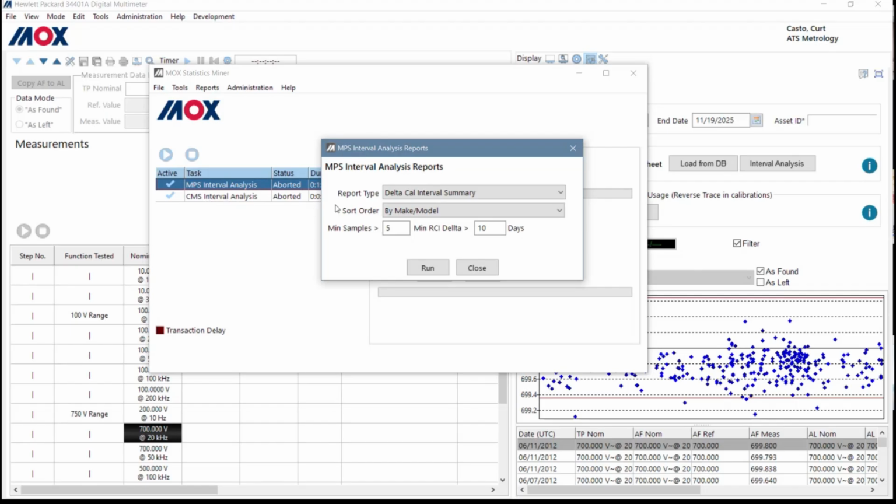And then of course, everyone talks about MPS and CMS. The CMS is your LIMS and the MPS is the part that processes the calibrations. Okay, so yeah, essentially the CMS is the go, no go, right? The whole calibration passed or failed, and MPS gets into more detail about the test points and all of that.